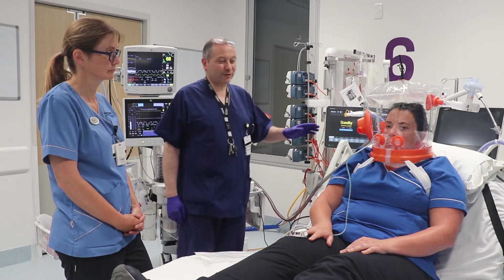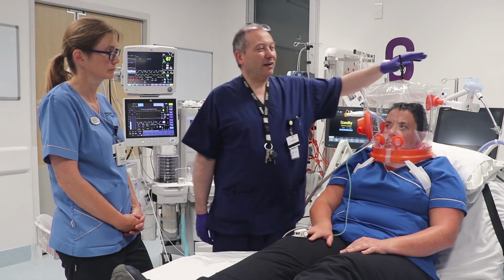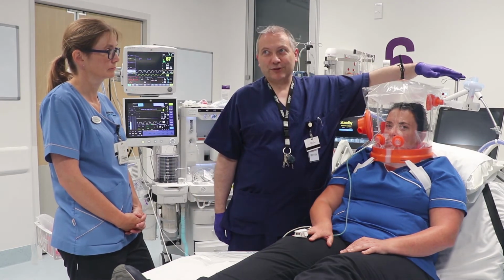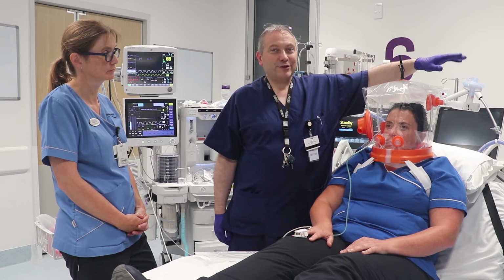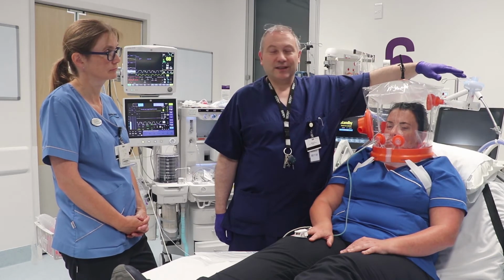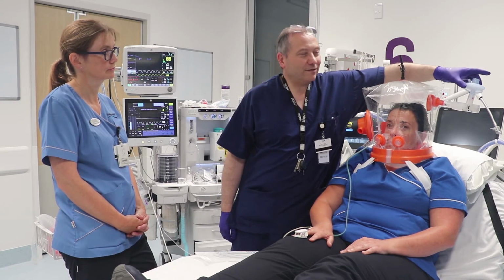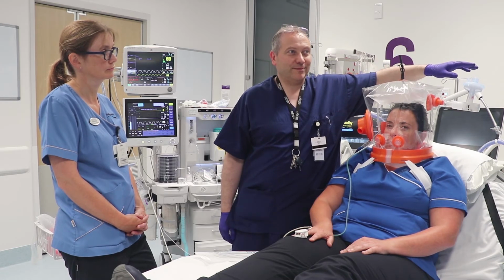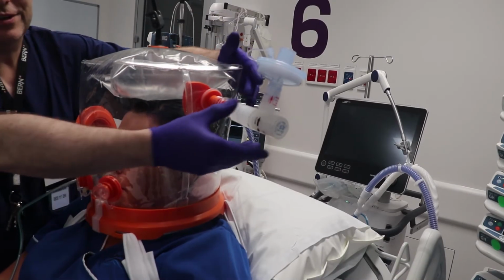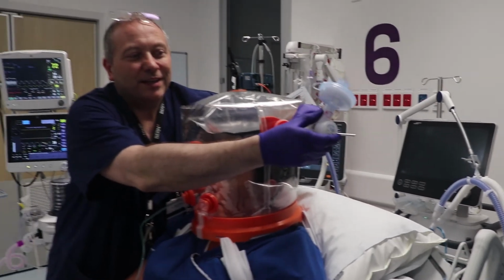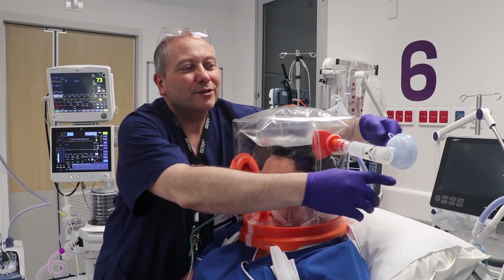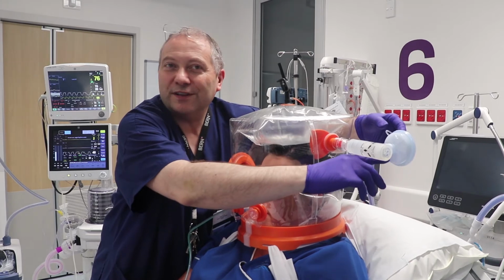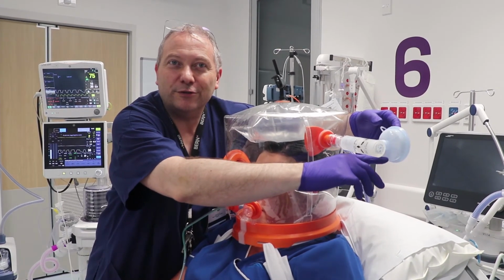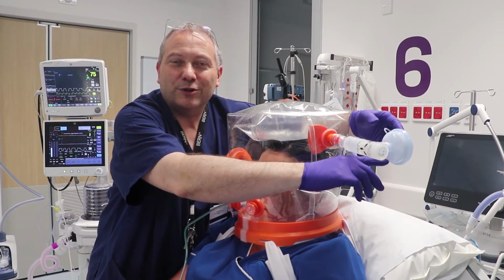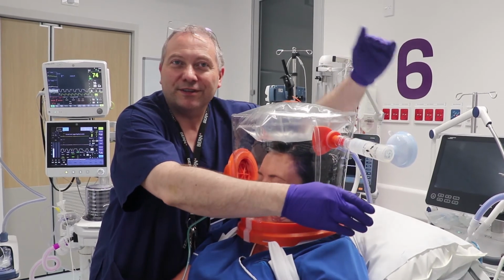Finally, it's very important to remember, if we have a viral filter on the expiratory port, that water can condense in the filter, and we should pay close attention that the filter is not wetting out. Often I prefer to keep the filter at an angle like that so that you can see the water developing and condensing out at a fluid level, which becomes more apparent than if it's in a vertical orientation.